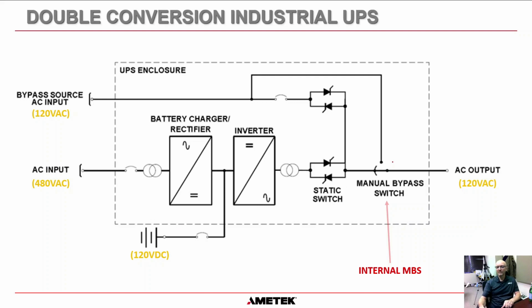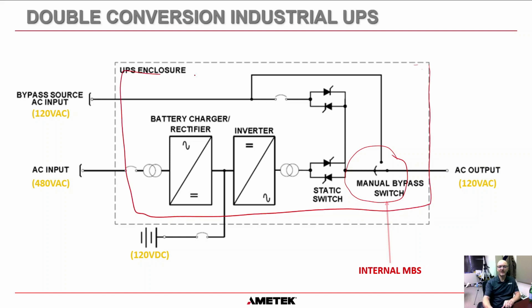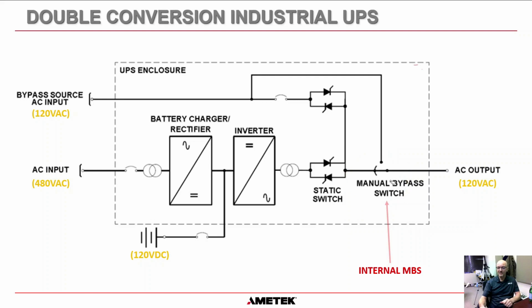But the most important thing that you can see here is the manual bypass switch is inside this box here. And this box here, excuse my terrible drawing, that box there is the actual UPS itself. Anything within those hashed lines are inside the UPS. So for this system here, the manual bypass switch is inside the UPS.